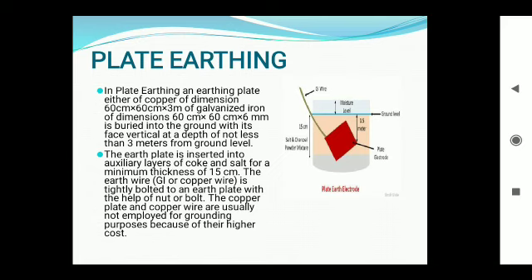The earth wire, which is made by GI, is tightly bolted to an earth plate with the help of nut or bolt. The copper plate and copper wires are usually not employed for grounding purpose because of their higher cost. And the 8 SWG earth wire is used for motor wiring, and 14 SWG earth wire is used for house wiring or for the low voltage wiring.